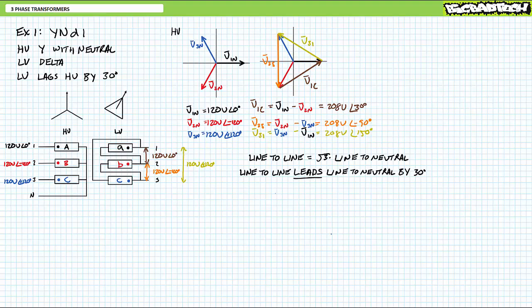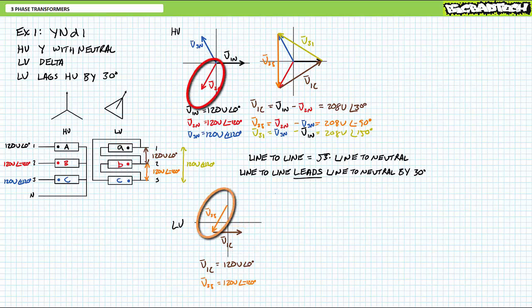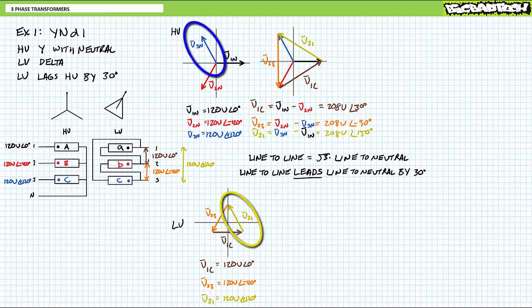Speaking of the low voltage side, let's do the same thing for it. Given we're using a transformer with a one-to-one turns ratio, low voltage winding lowercase a between lines one and two experiences 120 volts at an angle of zero degrees; winding lowercase b between lines two and three experiences 120 volts at an angle of negative 120 degrees; winding lowercase c between lines three and one experiences 120 volts at an angle of 120 degrees. Interestingly, these aren't line-to-neutral voltages anymore, but rather line-to-line values given the delta configuration. A YND1 configured transformer is effectively taking the line-to-neutral values of the high voltage Y and making them the line-to-line voltages of the low voltage delta.